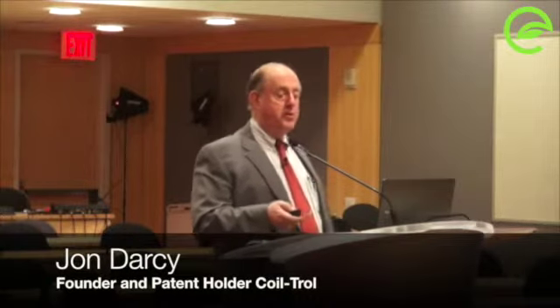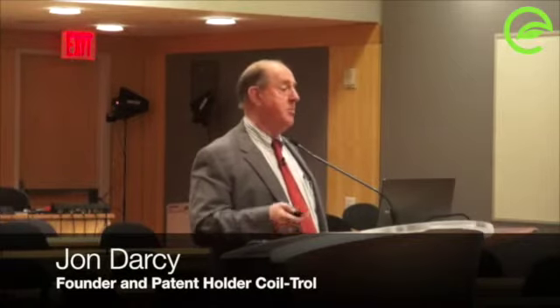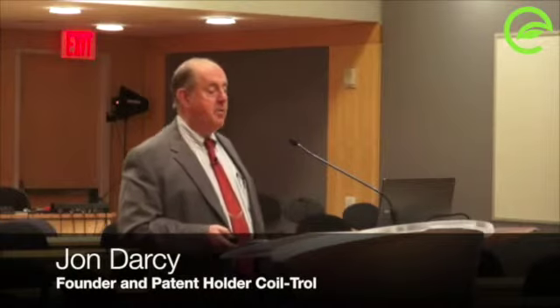We talked about putting additional chillers on. And the effort that it takes the engineers just to police that whole situation makes it a non-practical way of doing things. So most operators tend to limit it, bypass it, or completely shut off chill water reset. After putting in 1,000 of these things and going back and servicing them over the years, it was pretty clear to me that it is difficult. The systems I put in were a little bit better because I was doing something close to what this is, but not exactly the same.